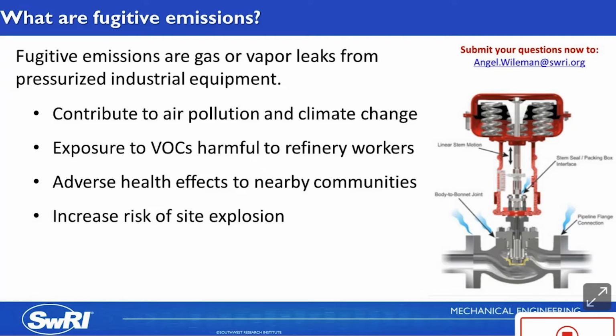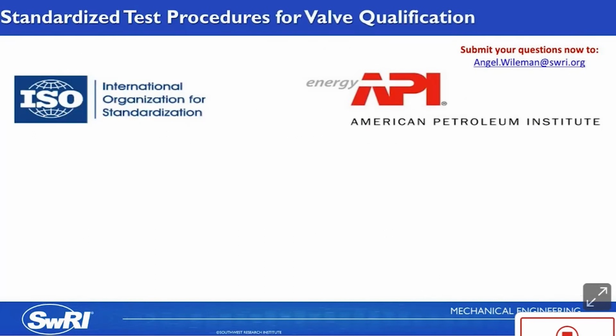So all of these considerations must be taken into effect while designing process valves for refineries. It's not enough to say that a valve was designed for low emissions based on CFD or sound engineering judgment. The risk is too great to assume that they will work for low emissions. So instead, let's put the valves to the test, recreate process conditions, and measure external leakage. And that's where the standardized test procedures for qualification come in. In order to lower emissions and meet requirements from the EPA or from local and state government authorities, end users want to install valves qualified for low emission service at their refineries.